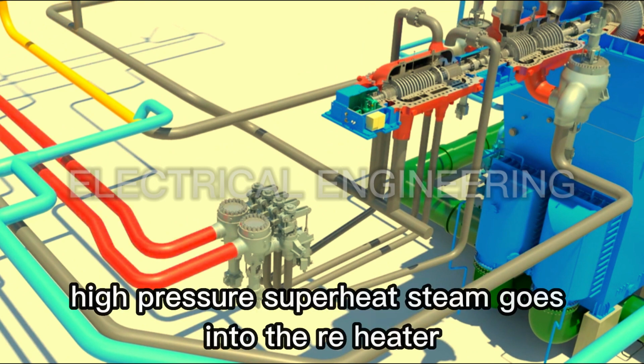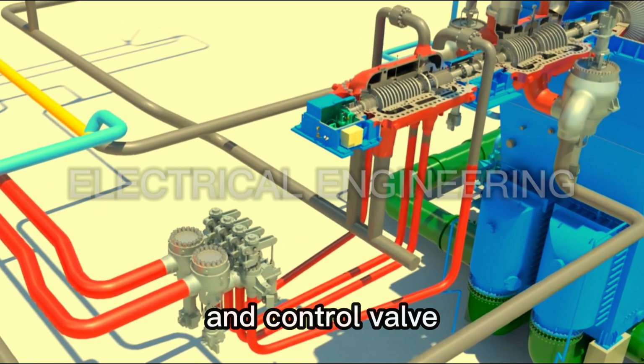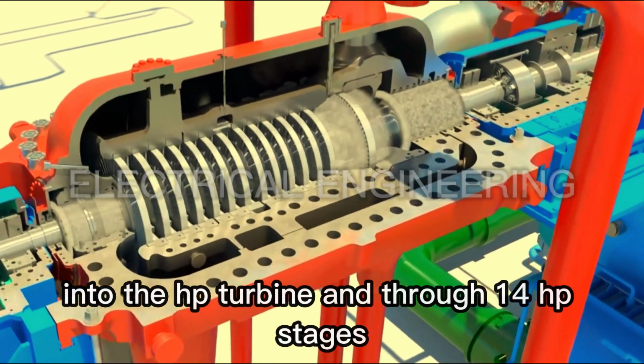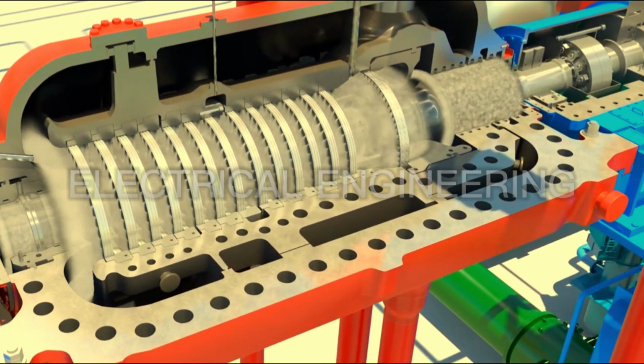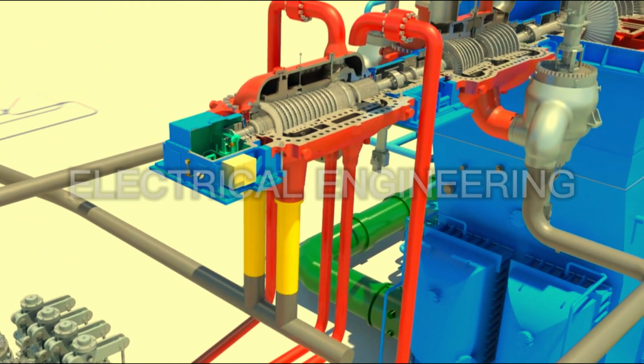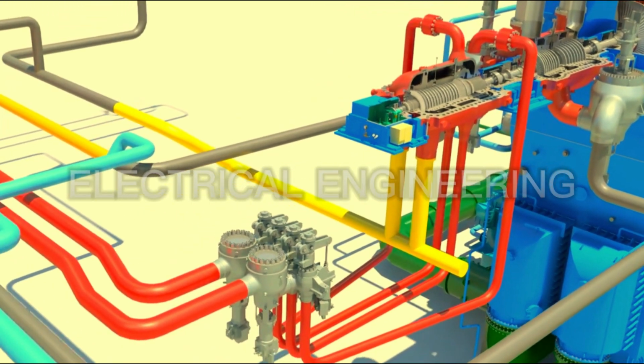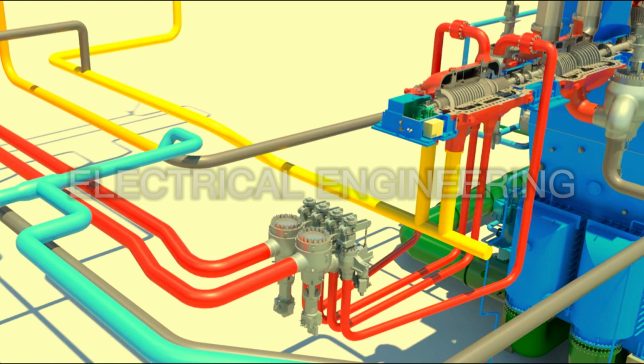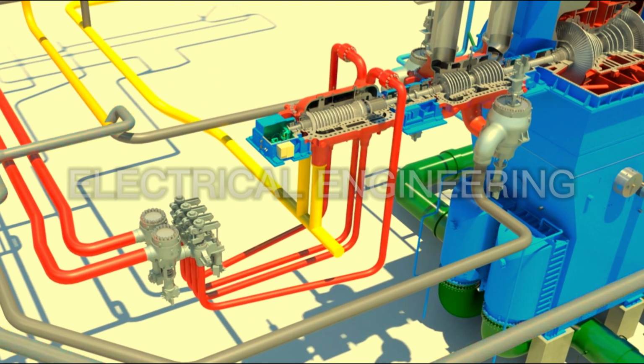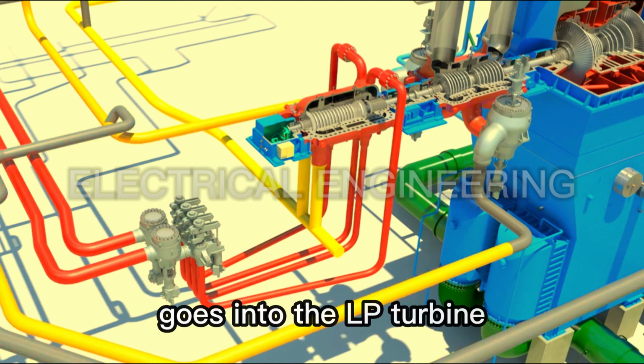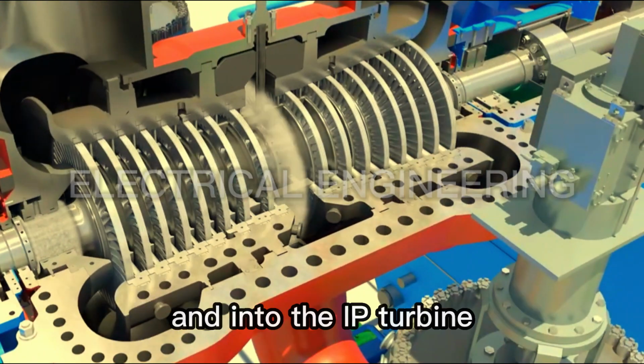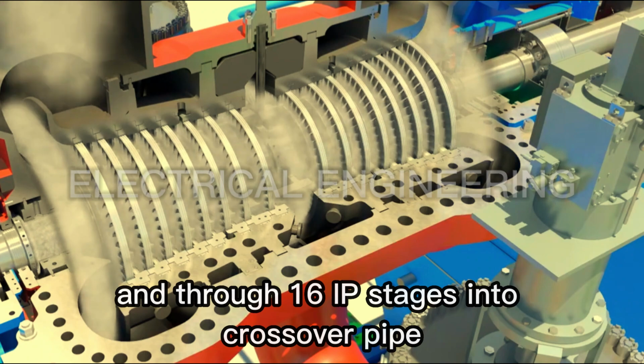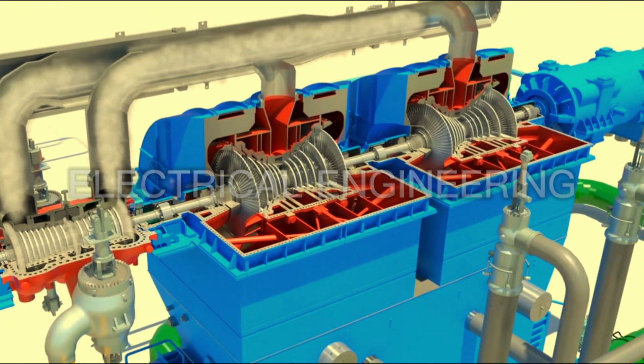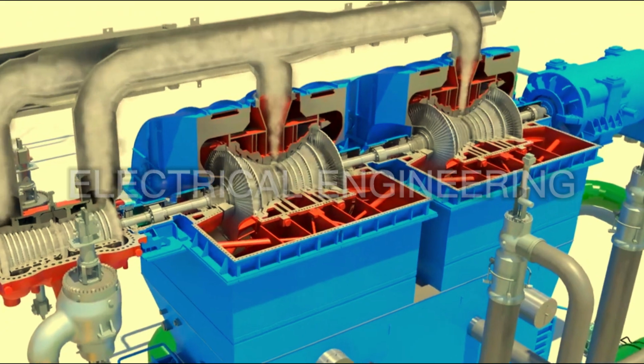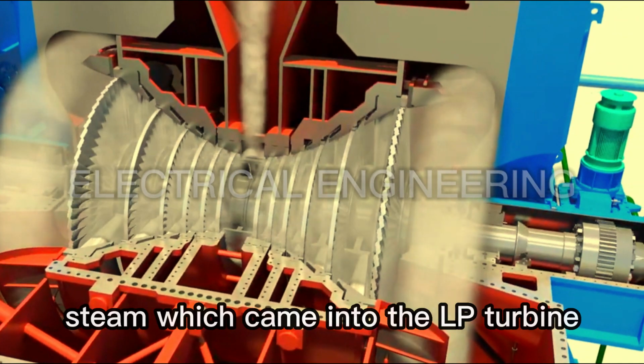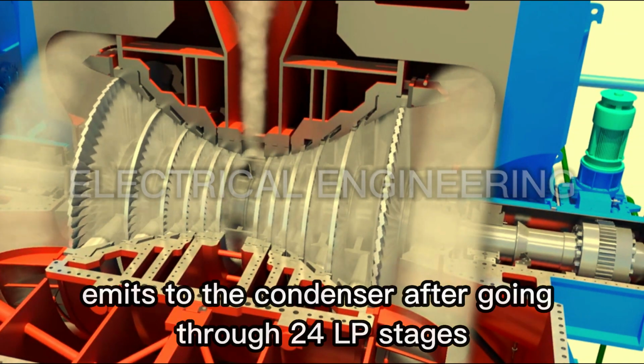High-quality, high-pressure superheat steam goes through the main stop valve and control valve into the HP turbine and through 14 HP stages. At the end of the turbine, steam which has been reheated at the reheater goes through the combined reheat valve into the IP turbine and through 16 IP stages into the crossover pipe. Steam which came into the LP turbine emits to the condenser after going through 24 LP stages.